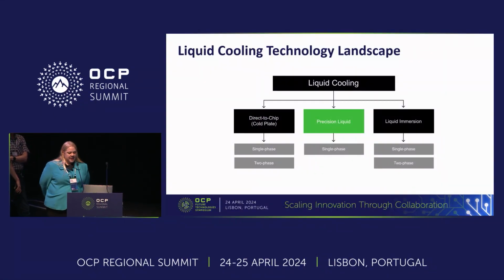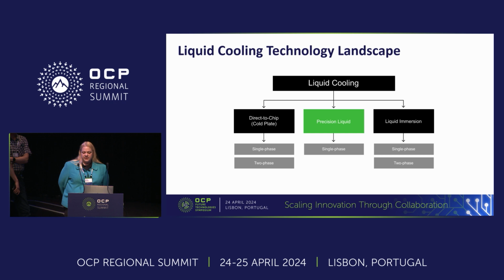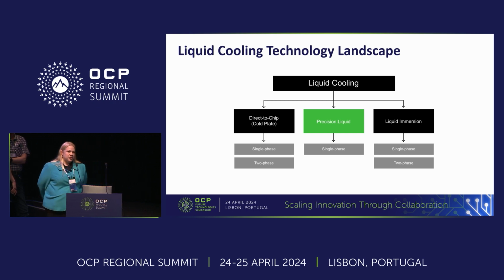Before we begin, I'd like to spend a little time on the liquid cooling technology landscape. Historically, there are two types of liquid cooling technology: direct-to-chip or cold plate, and liquid immersion. Cold plate technology typically uses a metal cold plate with either water or dielectric fluid to deliver component-level cooling to the hottest IT components, typically the CPU and the GPU. The remainder of the system is cooled with air using the existing infrastructure within the data hall.